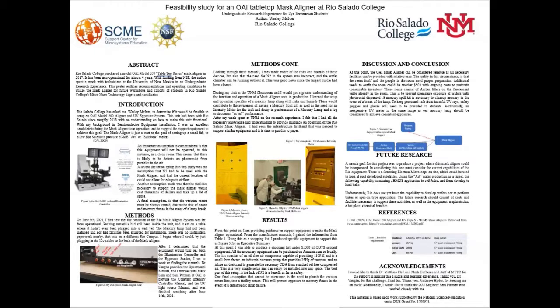The immediate hurdles to this research were known right away: the mask aligner will not be operated in any type of cleanroom, and this equipment requires N2 to operate, which is a health risk in the space it currently resides, a room about the size of a walk-in closet. I'm aware that most processes in the semiconductor industry require nitrogen to operate, and that the hazard posed by this gas must not be taken lightly.